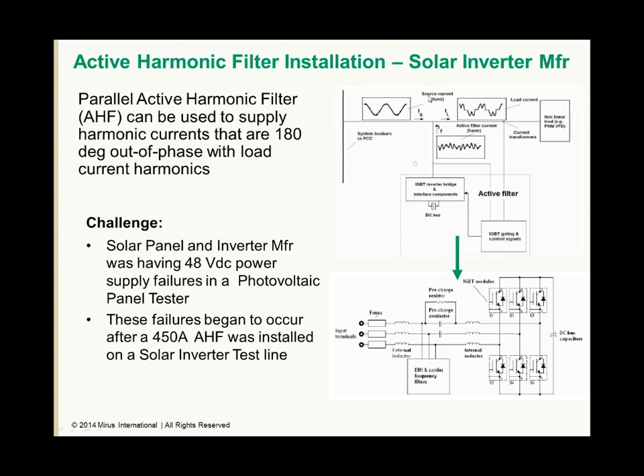So the slides are on this slide. On the right-hand side, it shows a schematic and the operation of a typical active filter, where you monitor the current being drawn by the nonlinear loads, and then the active filter, through its IGBT network, will inject currents that provide the harmonics that the load requires. Therefore, the power system only needs to supply the sinusoidal component, or the fundamental component. So, in an ideal operation, the active filter can be quite effective in reducing harmonics.